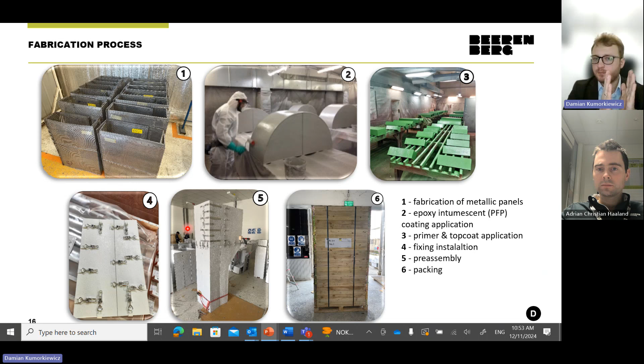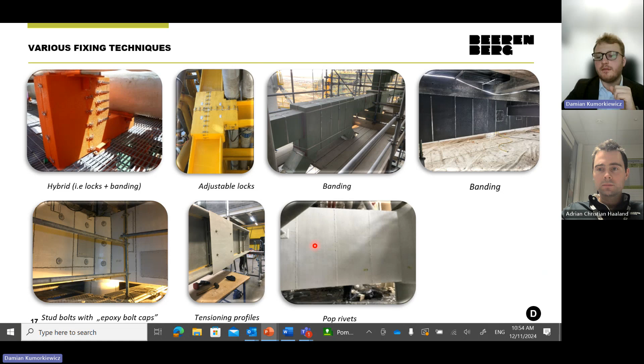Here's an example of various fixing techniques from different projects. This is a hybrid, a combination of lugs and banding. Then you have fully inspectable panels with adjustable lugs. Then a banding solution. Here you also have banding with stud bolts and epoxy bolt caps. When we use Hilti stud bolts, we also have to protect the bolts from outside with what we call epoxy caps. Here you have a couple of cases: tensioning profiles, used when welding isn't allowed for 1, 2, or 3-sided PFP, for example, and pop rivets, which is currently the cheapest fixing method available.